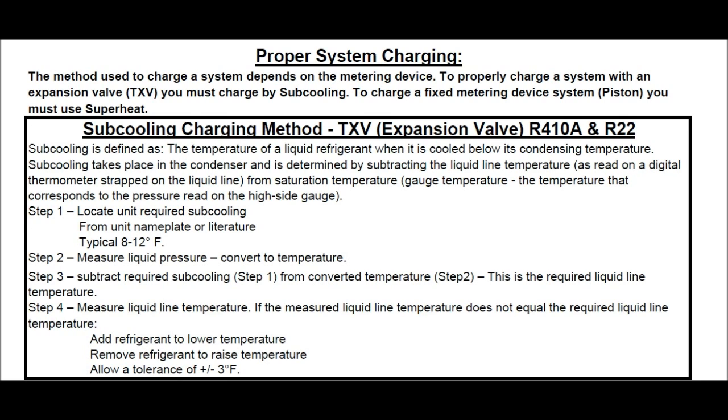Step one: Locate the unit's required subcooling from the unit nameplate or the literature. Typically it's going to be between 8 and 12 degrees Fahrenheit. Step two: Measure liquid pressure and convert to temperature using a PT chart or your refrigerant gauge.